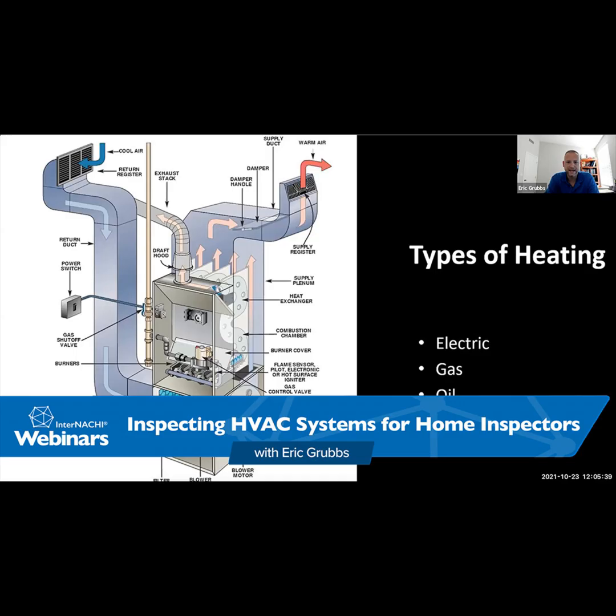These things do happen. Furnace isn't operating properly. The flues get too hot or out of spec. Maybe a technician was working on it, couldn't figure out the problem, but knew safety was the problem, so he jumpered it out. And next thing you know, the house burns down because something caught on fire or it wasn't installed properly. And ironically, as much as I've been in this field, you do see a lot of companies and a lot of technicians that really don't know how to install some of this equipment.